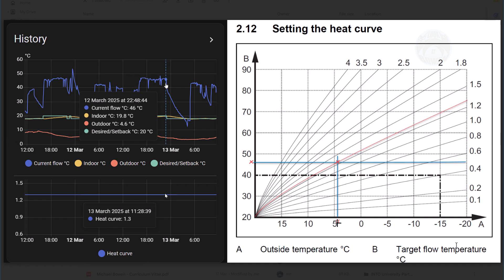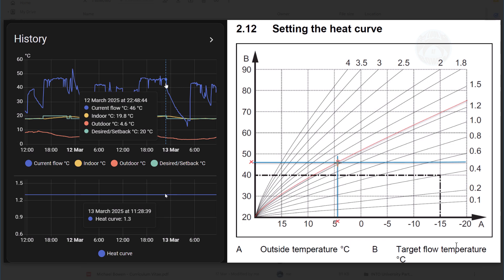And where it crosses on the red line, that is basically what the desired temperature should be. Now, if you look at my desired temperature of 20 and then you look at the indoor temperature, I'm achieving a 19.8. That's only 0.2 degrees away from this target temperature. So with that information, I now know that the heat curve that I'm on is almost spot on.